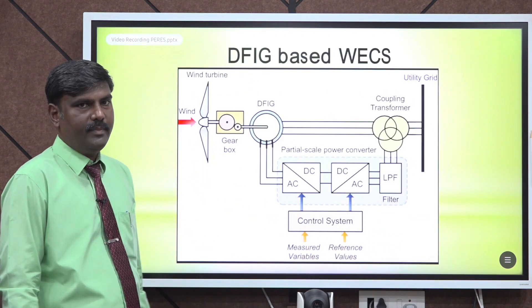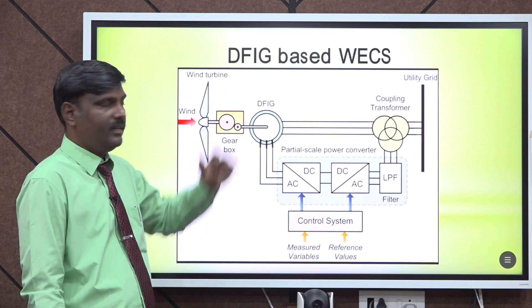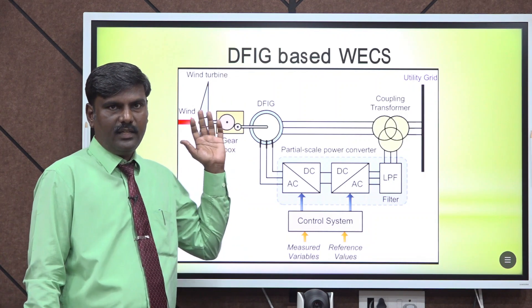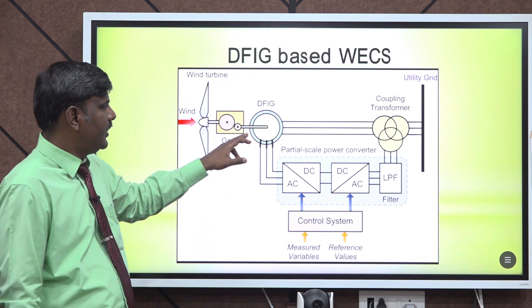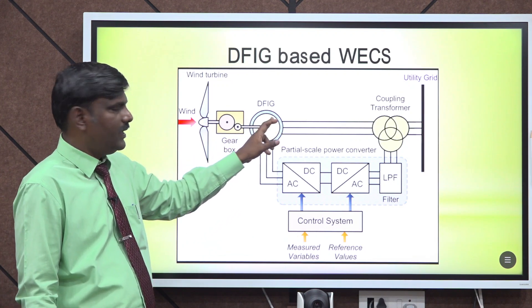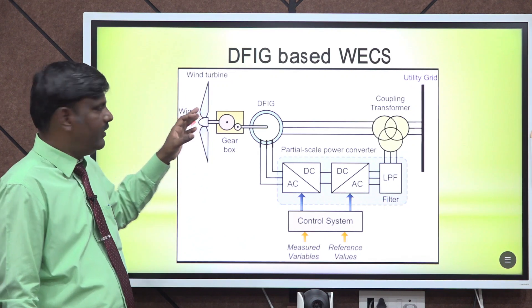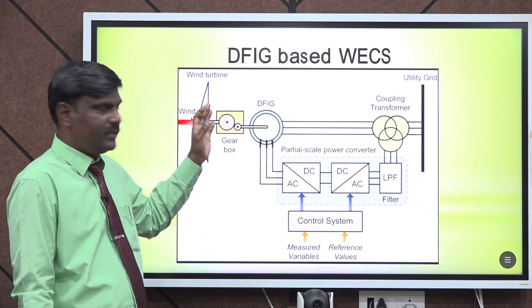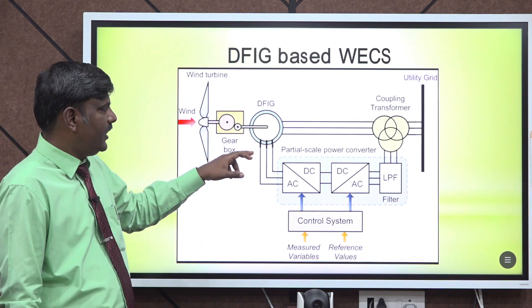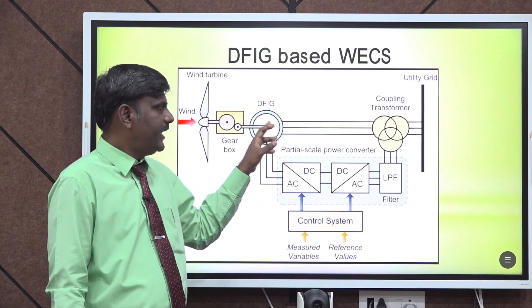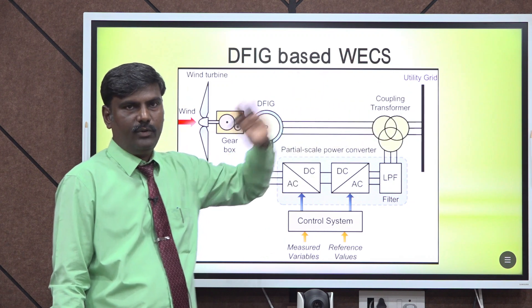Next we see DFIG based wind energy conversion system. DFIG is nothing but doubly fed induction generator — this generator is nothing but a slip ring induction motor based generator. In a slip ring induction motor, connections are established from the rotor as well as the stator. As with the squirrel cage induction motor, we receive wind power with the help of a turbine and then through a gearbox we connect the shaft of the DFIG. In the stator line there is no power converter — it is directly fed to the transformer and from the transformer it is fed to the utility grid.